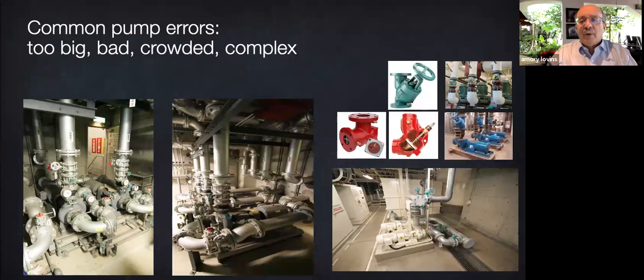Endemic oversizing is often claimed to be needed for flexibility, but just spec the right size now and then design for flexibility. Put in a pad and piping so you can fit a bigger pump if you later need it. But if you don't need it yet, maybe you don't put it in yet. Pumps and pipes are often crammed into tight spaces, as in these photos on the left, or laid out as if they were. So the constrained so-called entering and leaving conditions, pipe bends and fittings that are too close into the pump, cause major turbulence, killing the pump's efficiency and often causing impellers or seals to fail early.